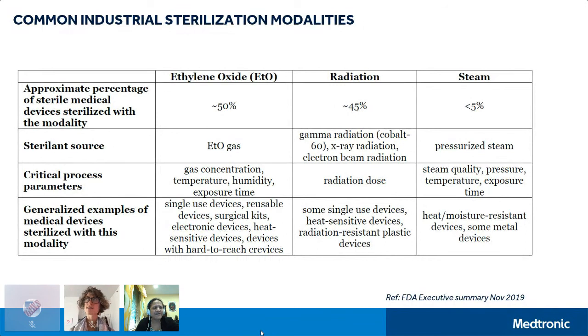It's considered favorable for use in processes because of its short processing time and better penetration, and also compatibility with a wider variety of materials, although that is less than ETO. One of the bigger advantages of using a radiation-based method is that the process parameters that you see here, gas concentration, temperature, humidity, or exposure time, we don't have any of those process parameters that would affect your material compatibility. And then the radiation dose is pretty well established.